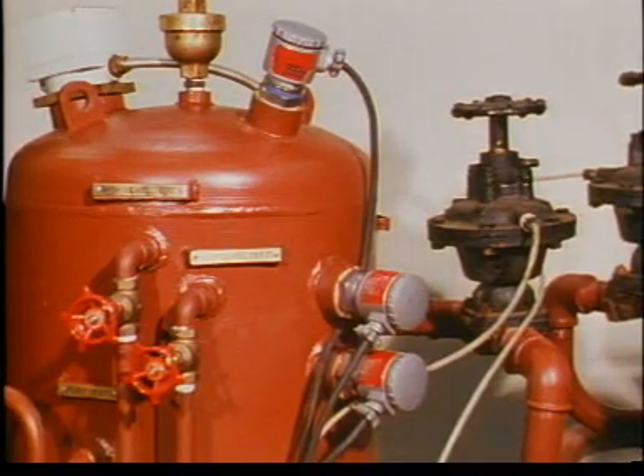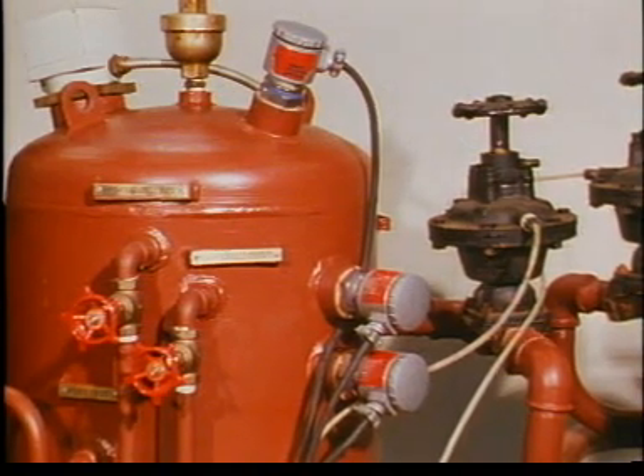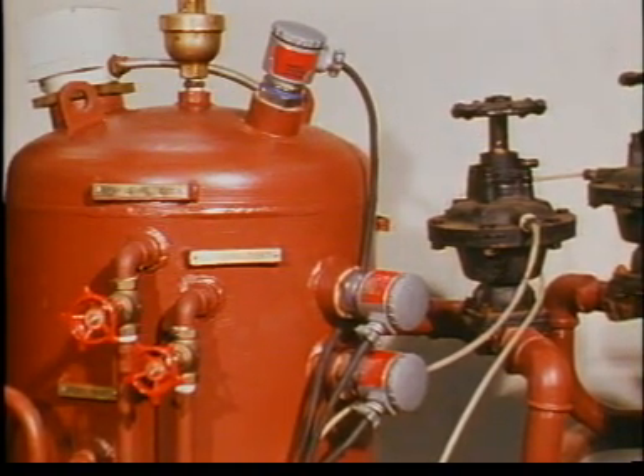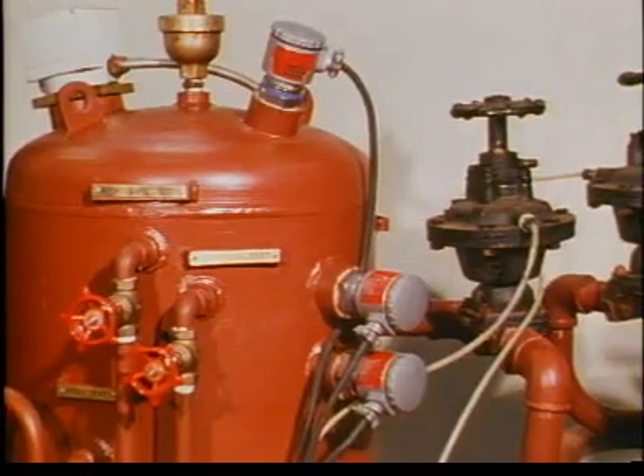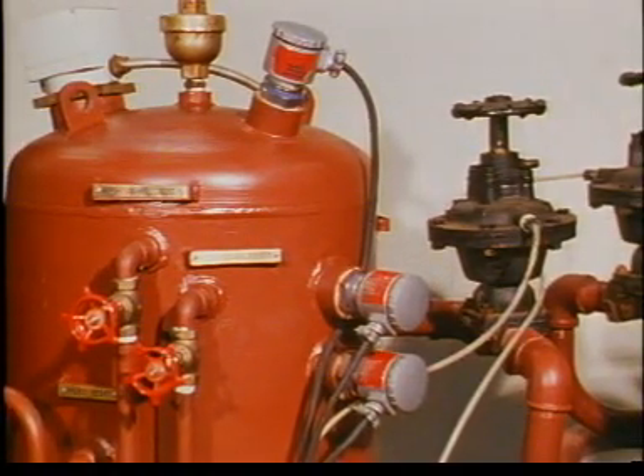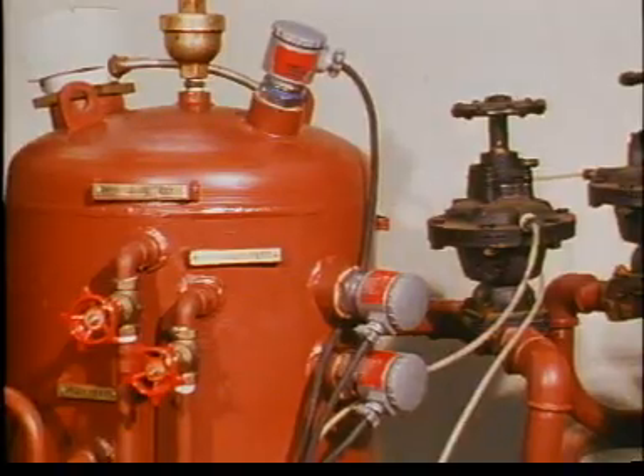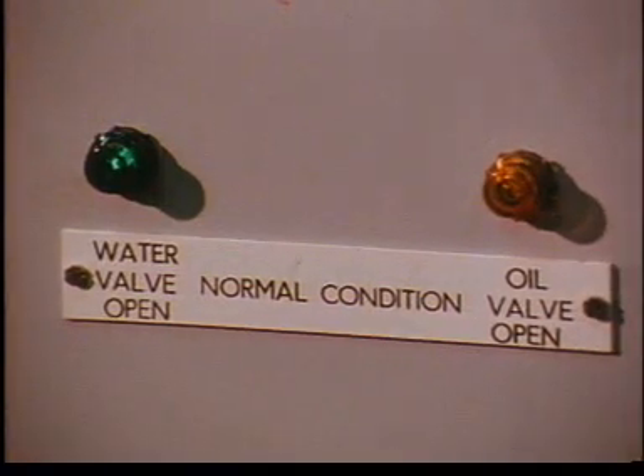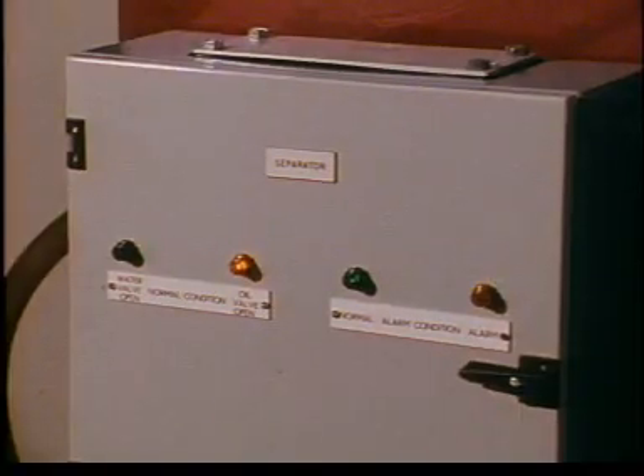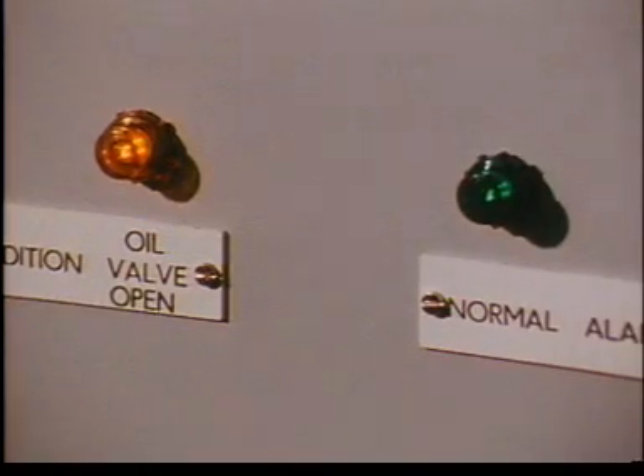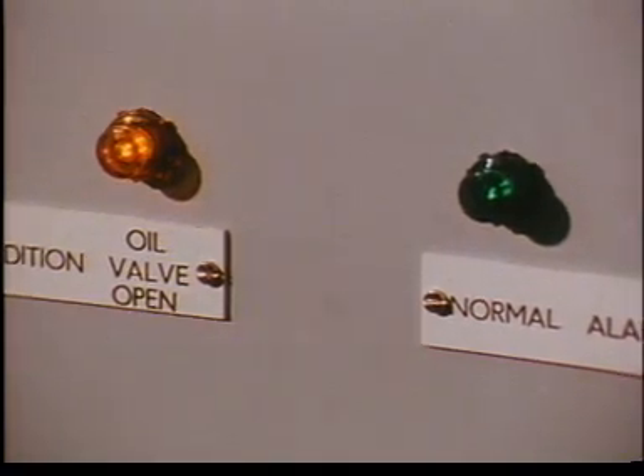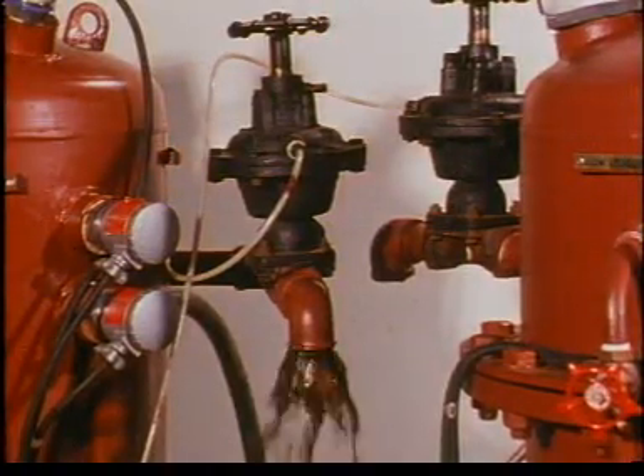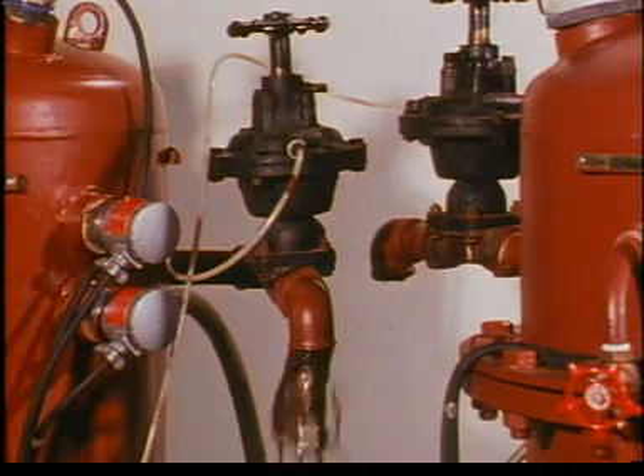These three probes at different levels measure the dielectric constant of the liquid in which their inner ends are immersed. This constant is different for water and oil. When the probe is immersed in water, an indicator light will be illuminated on the control panel. When in oil, another indicator light shows. Here we can see that the high-level probe is immersed in oil and the low-level probe is immersed in water. In this situation, the outlet valve will be open and the oil will be flowing into the oil storage tank.